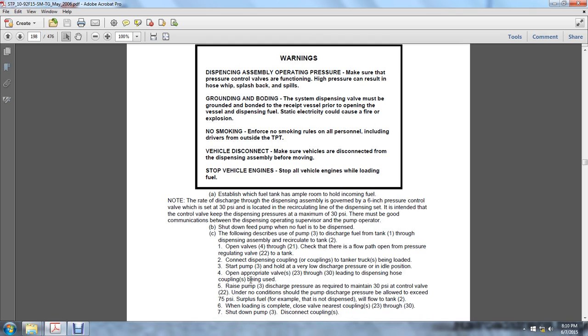The rate of discharge through the dispensing assembly is governed by the 6-inch pressure control valve. It is set at 30 psi and is located in the recirculating line of the dispensing set. The control valve is intended to keep the dispensing pressure at a maximum of 30 psi. There must be good communication between the dispensing operation supervisor and the pump operator. Shut down the feed pump when no fuel is being dispensed.